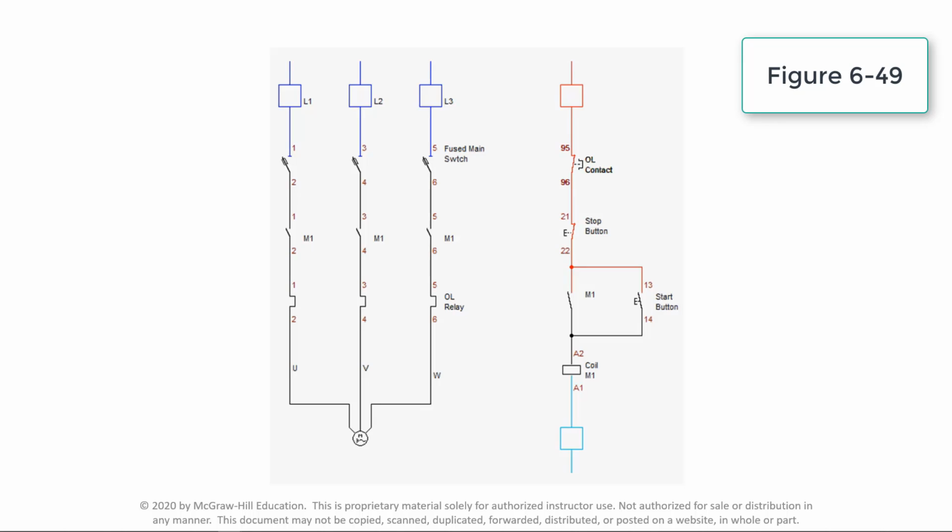This video demonstrates the operation of an IEC motor control schematic as compared to the equivalent NEMA schematic. The IEC starter schematic has power terminals marked 1-3-5 and 2-4-6, corresponding in function to L1, L2, L3, and T1, T2, and T3 on the NEMA starter schematic.